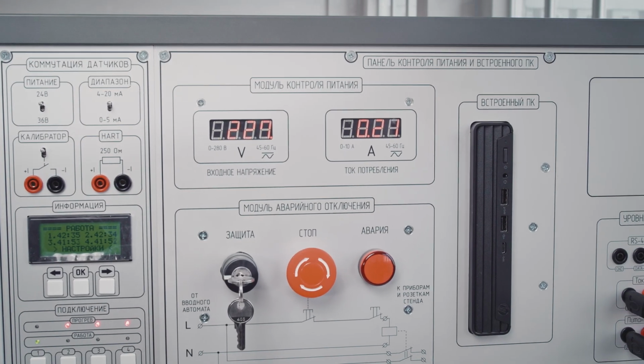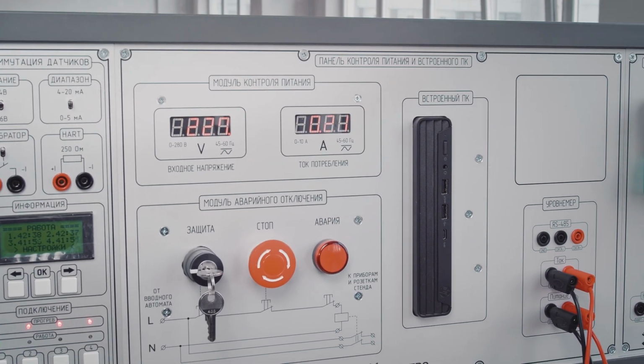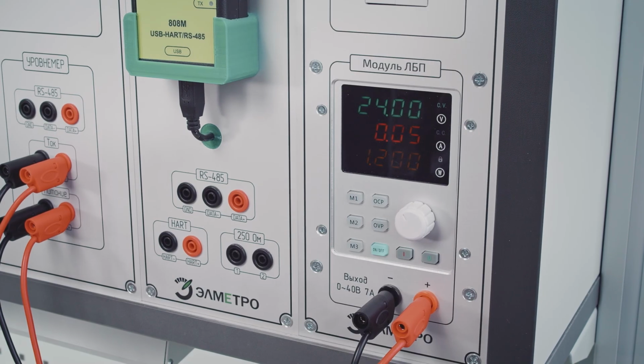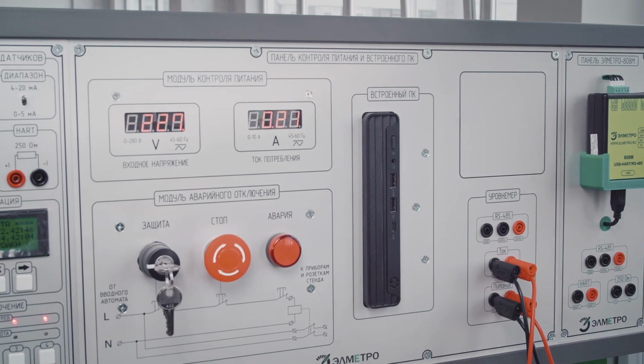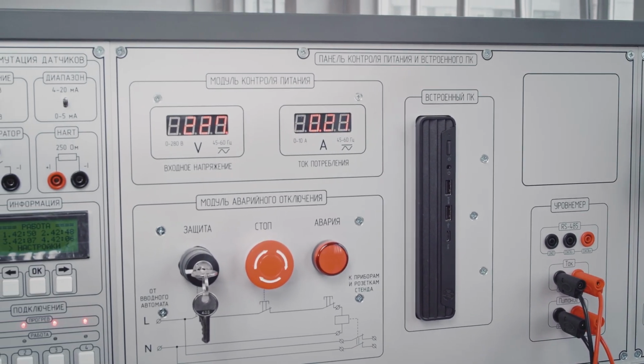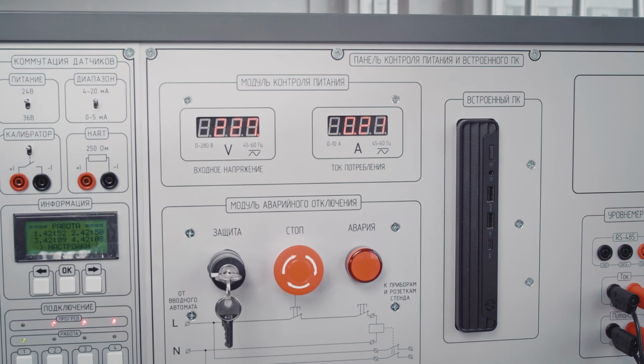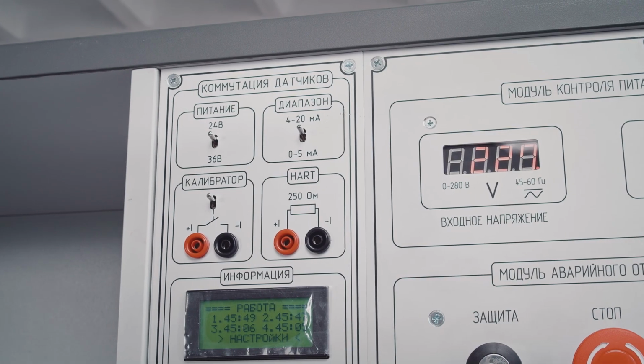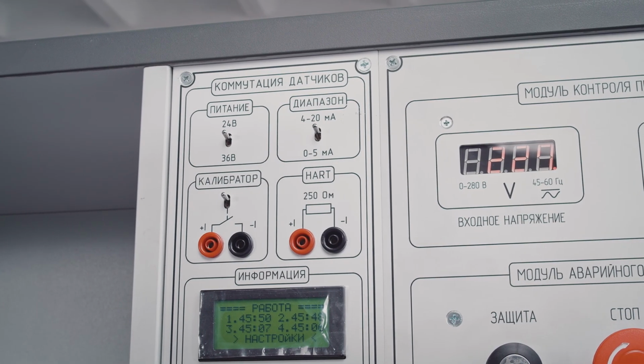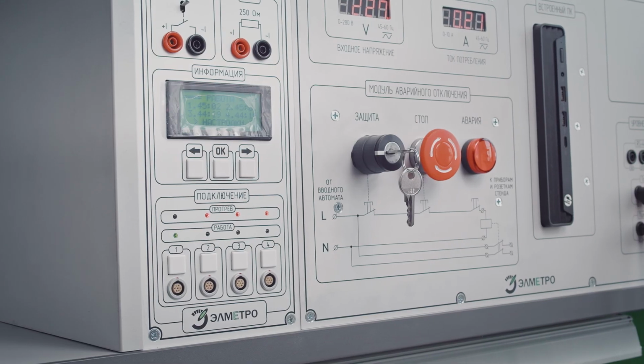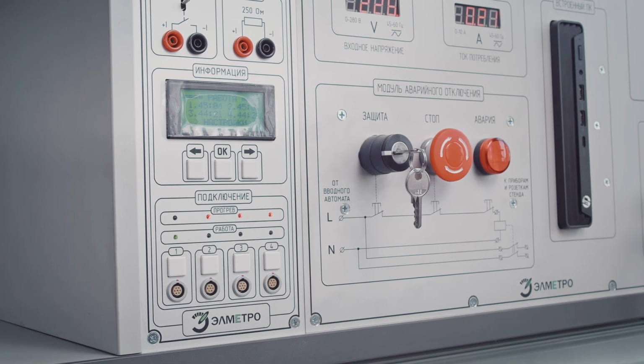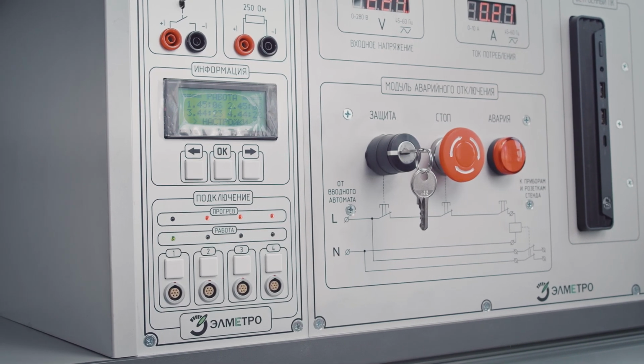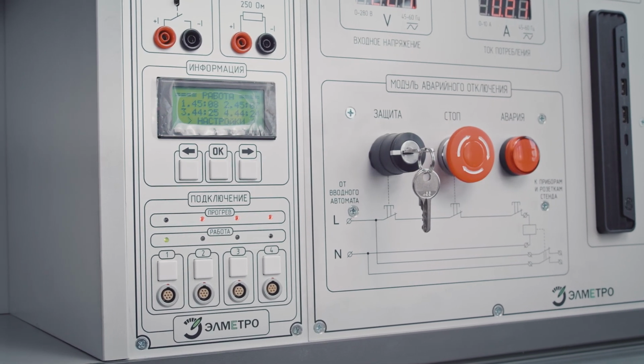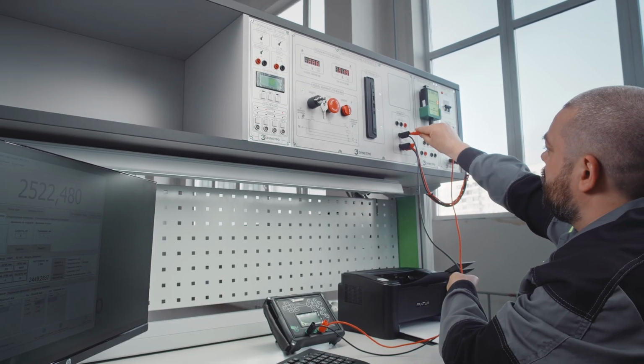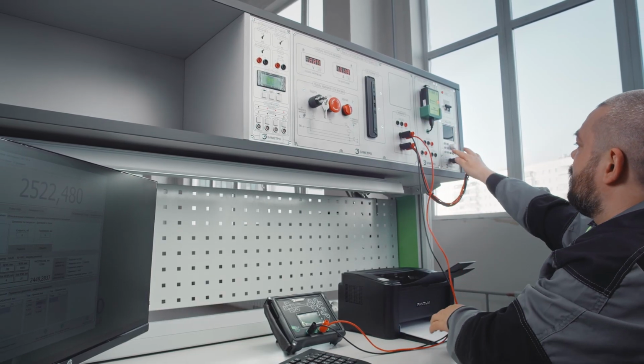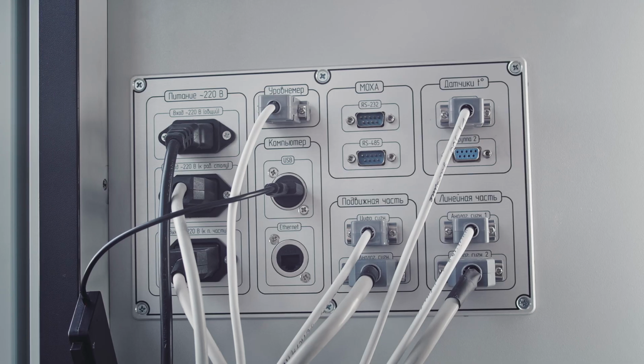It accommodates different pieces of equipment for the bench control: the laboratory power supply block, the module for controlling and monitoring the bench power supply and for the protection from unauthorized access, as well as the module for verifying the alarm actuation of the instruments. The connection panel has 4 channels for simultaneous verification and warm-up of 3 level instruments. The superstructure is used to install multi-channel high-precision multimeters.